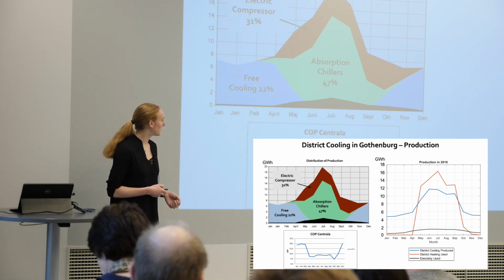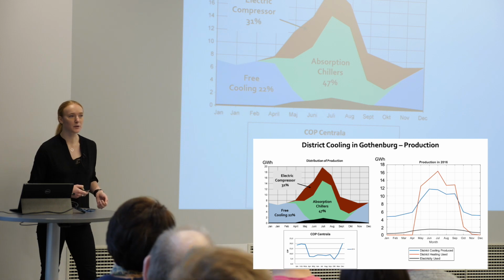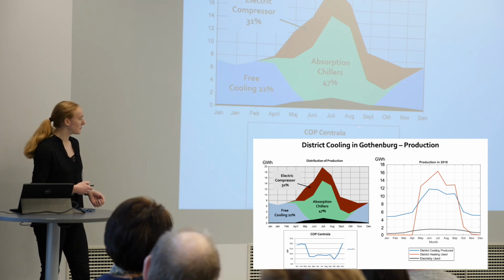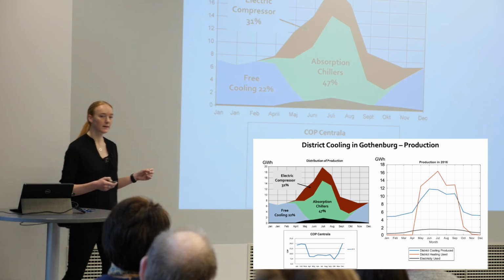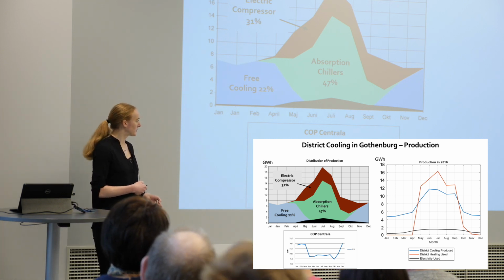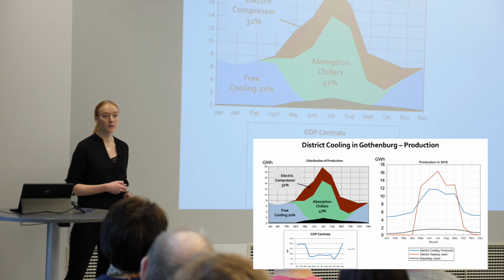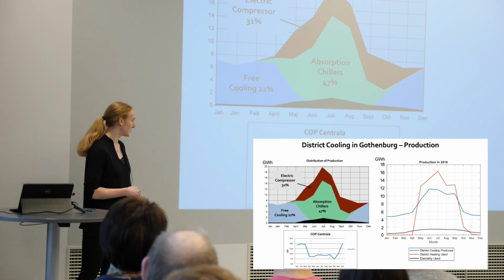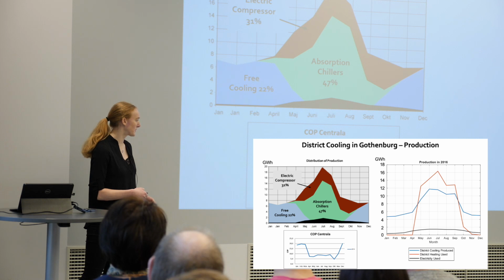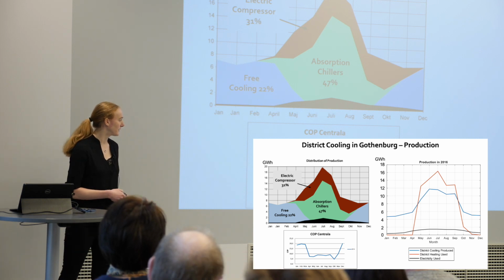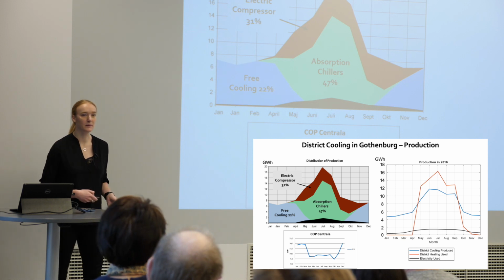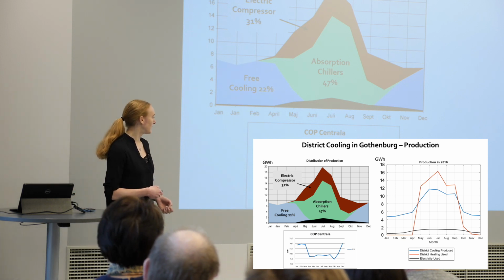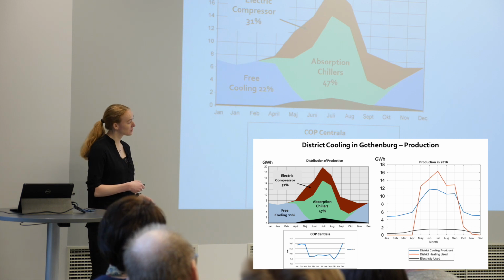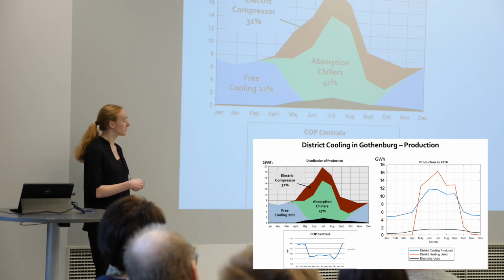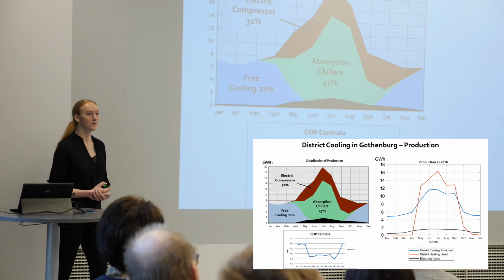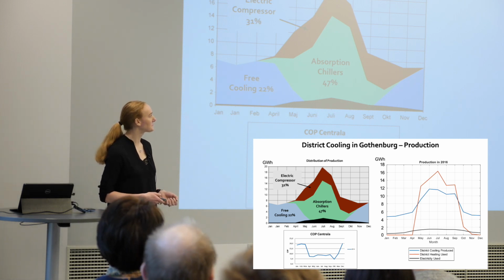And just to give you a sense of how well the system performs throughout the year, the COP for the large system in Gothenburg is actually up to around 20 in the winter when the free cooling is used. And then it drops down to around 7 in the spring and summer, and then it does a little bit of a dip here when there's a lot of compressors in the beginning of fall. But in the winter, the COP gets really high, and this includes also the distribution pumps. So not only the chillers in the system, but everything combined.